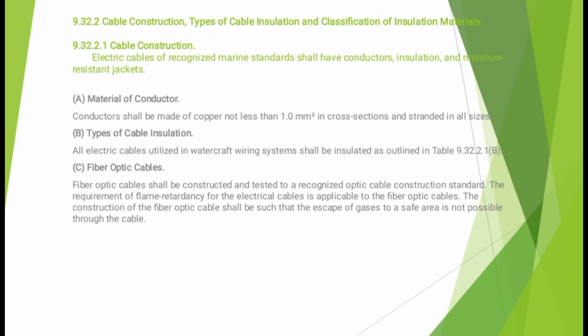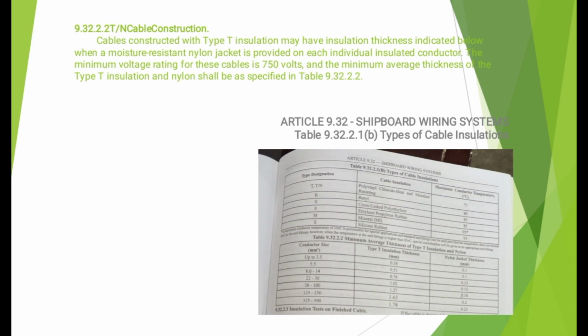All electrical cables in watercraft wiring systems must be insulated, ensuring safety and reliability in wet environments. Cables constructed with the Type T insulation may have insulation thickness indicated below. When a moisture-resistant nylon jacket is provided on each individual insulated conductor, the minimum voltage rating for this cable is 750 volts, and the minimum average thickness of the Type T insulation and nylon shall be as specified in Table 9.32.2.2. So, as we can see in the table, cables constructed with Type T insulation featuring a moisture-resistant nylon jacket on each insulated conductor must possess a minimum voltage rating of 750 volts with the average thickness of both the Type T insulation and nylon jacket.